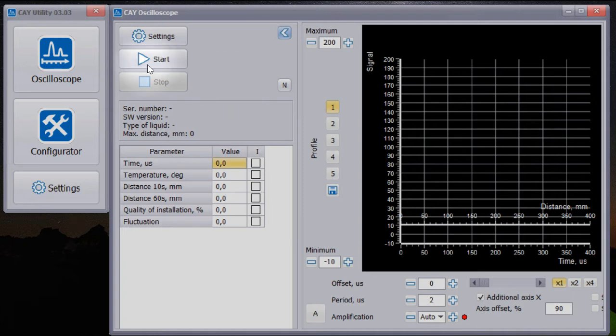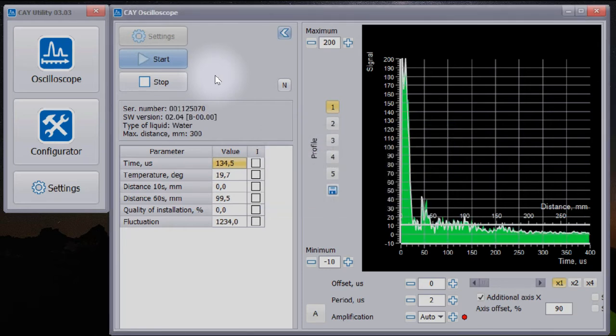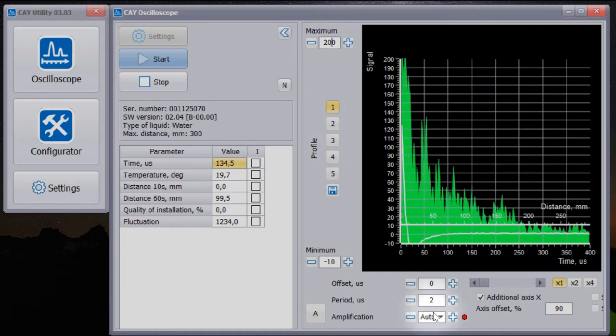That's how we find the best installation place. Connecting the sensor. It is advised to set the maximum amplification coefficient during this phase. Put acoustic gel on the sensor surface. Trying to attach the sensor to the tank bottom. Here we can see some peaks of signal. They are caused by reflections. The more reflections, the better. We can scale this axis to see more.